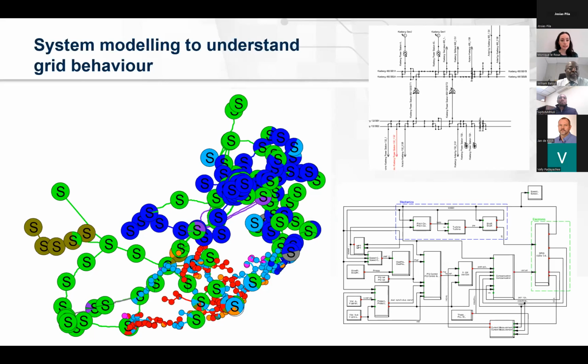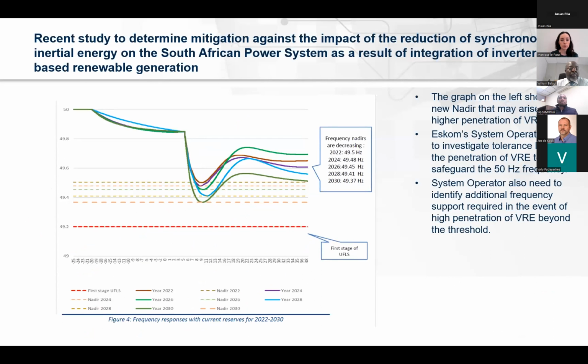Again, this is just a study that we recently undertook with Eskom to determine mitigation against the impact of reduction of synchronous generators and the reduction of inertial energy in South Africa as renewable energy generators are scaled up on the grid. So this is a result of the software that we used there. We looked at the various years, 2022 to 2030, and then as renewable energy increases throughout those years, according to the IRP 2019 roadmap, we can see exactly how that impacts your system stability and your system frequency.